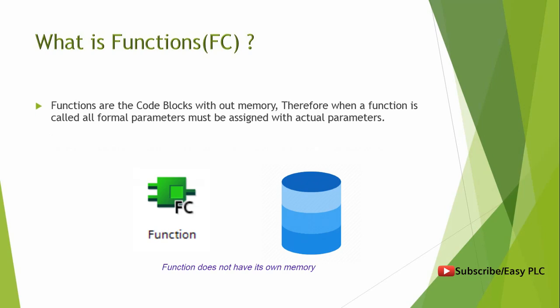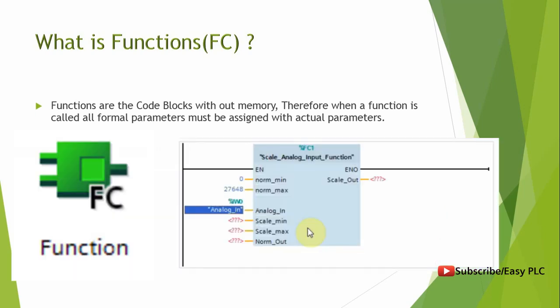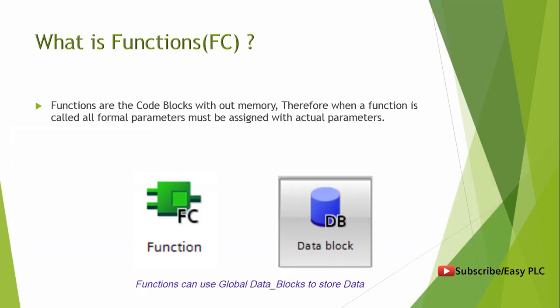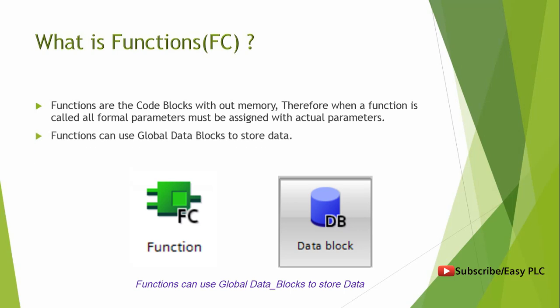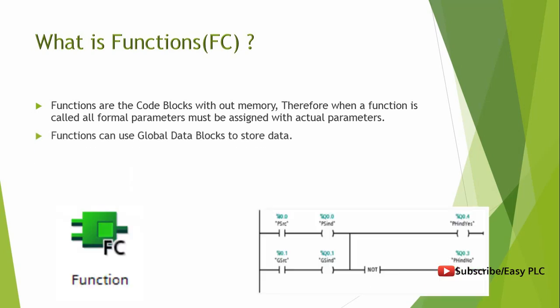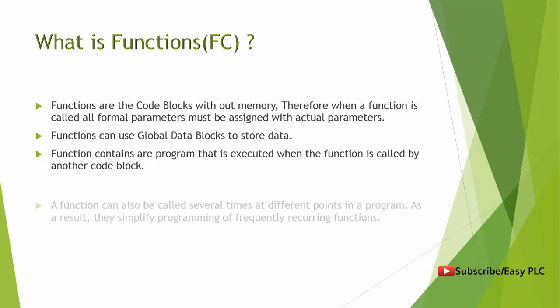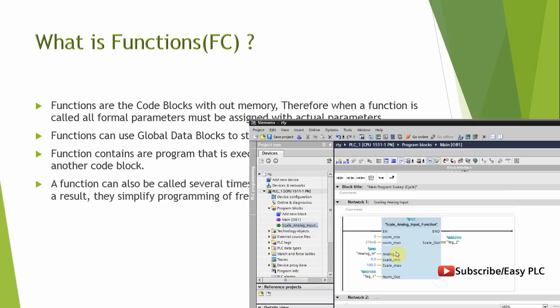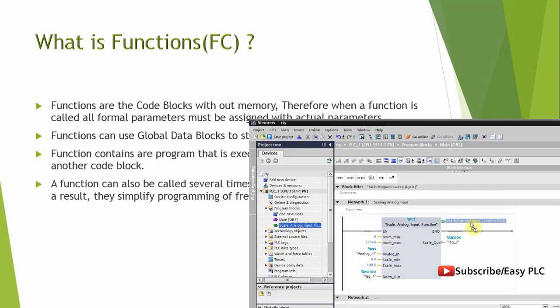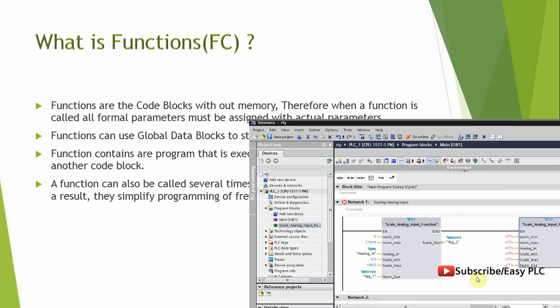Functions are code blocks without memory. Therefore, when a function is called, all formal parameters must be assigned with actual parameters. Functions can use global data blocks to store data. A function contains a program that is executed when called by another code block. A function can also be called several times at different points in a program, simplifying the programming of frequently recurring functions.